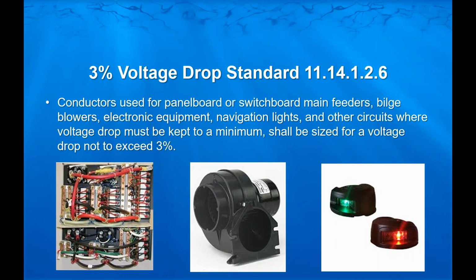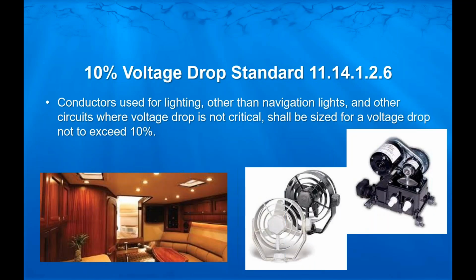So conductors that are used for panel board or switchboard feeders, bilge blowers, electronic equipment, navigation lights, and other circuits where voltage drop has got to be kept to a minimum, that wire shall be sized for a voltage drop not to exceed 3%. And we'll see in a minute what size wire we're talking about here to be able to accommodate that. Conductors used for lighting other than nav lights and other circuits where voltage drop is not critical shall be sized for a voltage drop not to exceed 10%. So even in the cases we're not trying to hold that voltage drop to 3% for critical items, we don't want it to go over 10%.